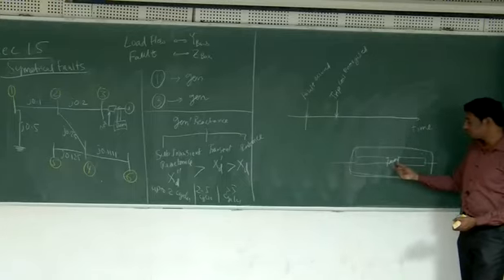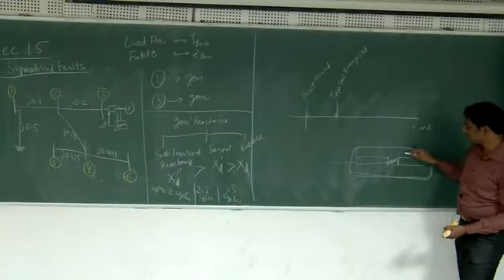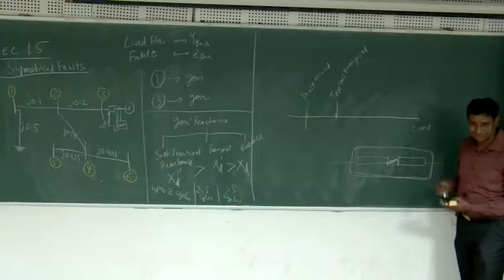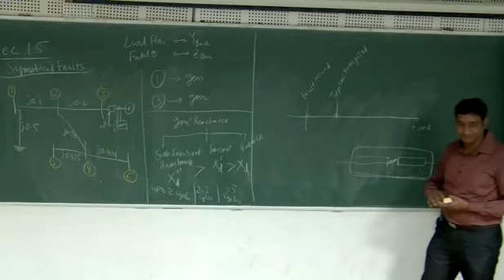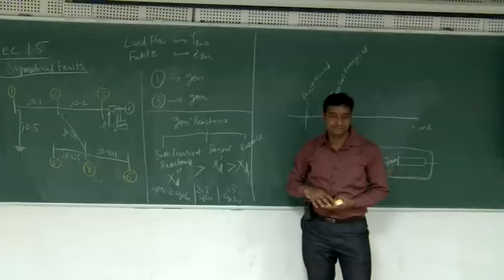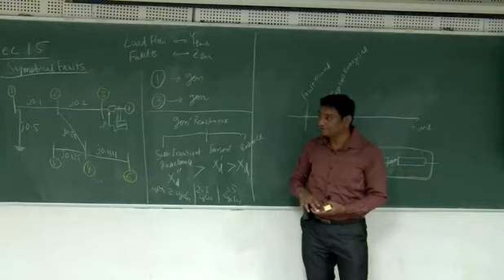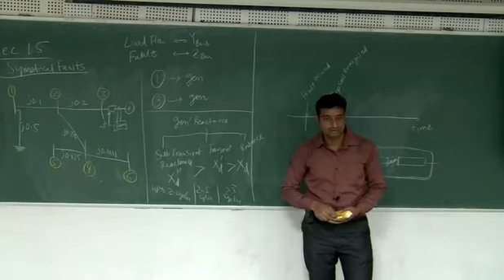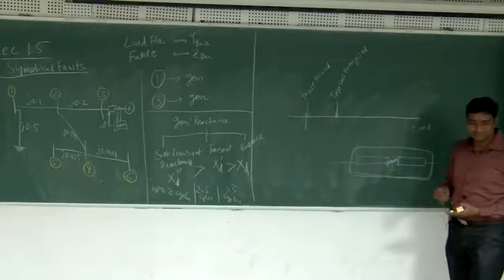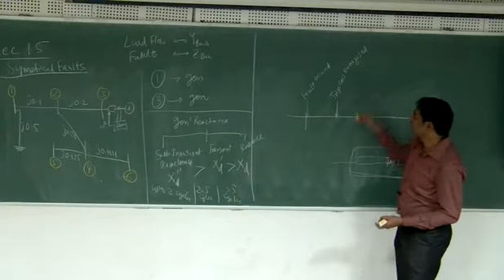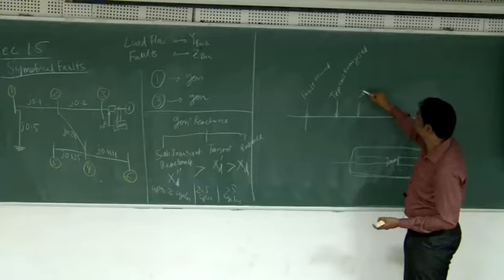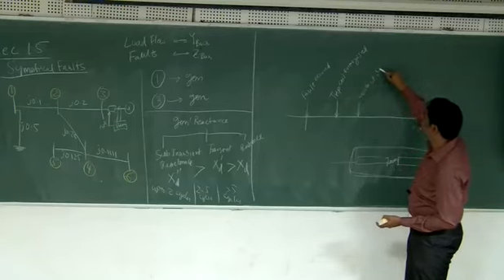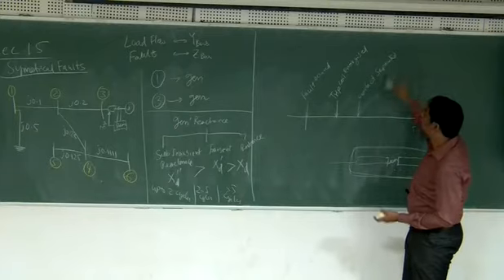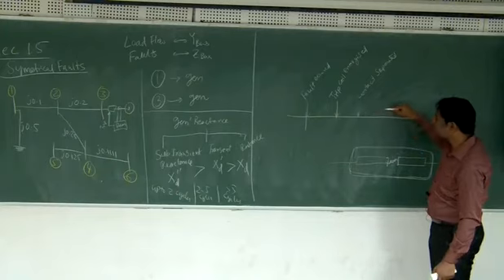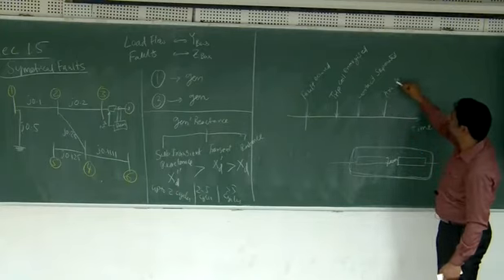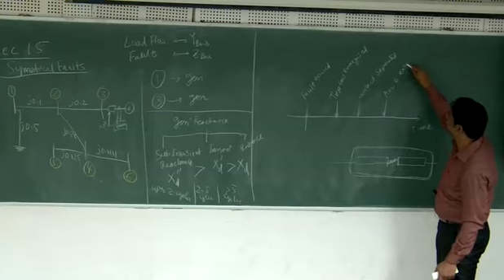After some time the arc will be extinguished because of the gas or oil that is present, and so on. So this arc is always there. Even with the switch that you use in your house, when you switch on the light or fan, that arc is always there. It will be there for very few milliseconds. So once the trip coil is energized, the contacts are separated, and then the arc will start, and after some time the arc is extinguished.